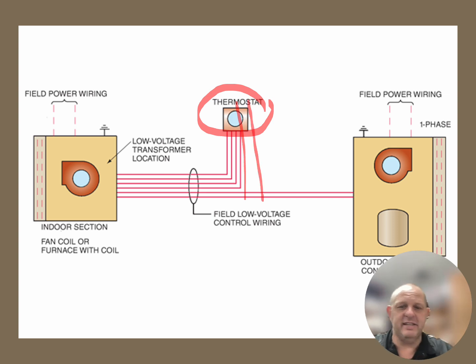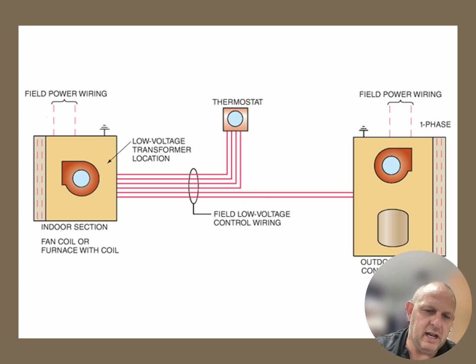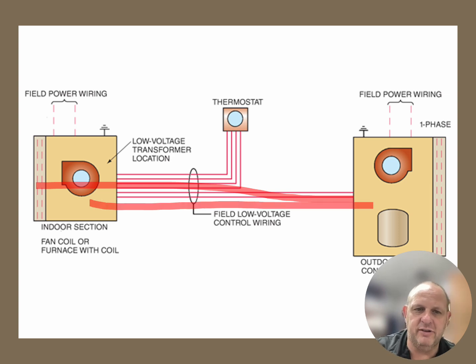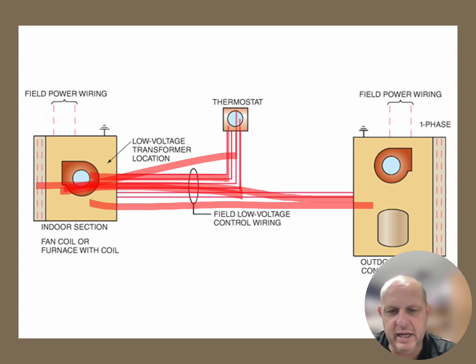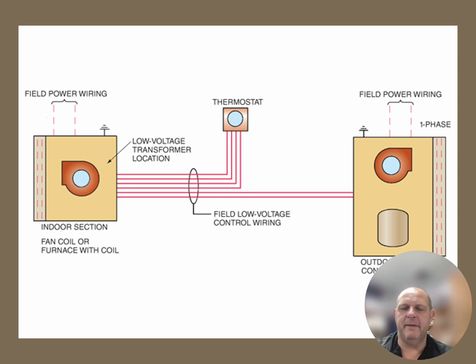Because I want accessibility to those wires. So I'm going to run those wires from the outdoor unit all the way into the indoor unit. The second thing I'm going to do is take the thermostat wires and run them down into the indoor unit in a nice, clean way. The purpose for that is so that I can quickly check with my multimeter or by touching wires together what system components should be running or should not be running at that particular time. It's hard for me to pull the thermostat off the wall to get behind there to check those wires on that particular unit. So I never ever want to make my connections at the thermostat. I want to make all of my low voltage connections at the indoor unit.